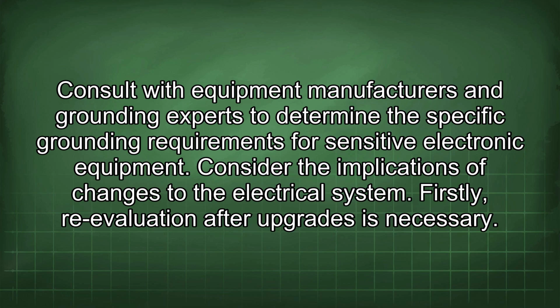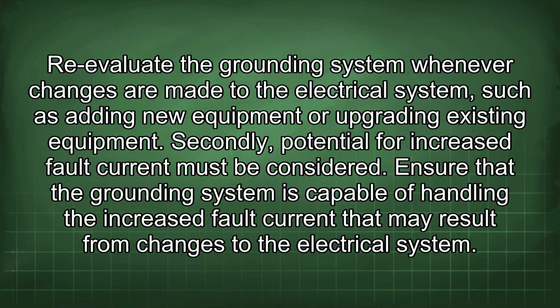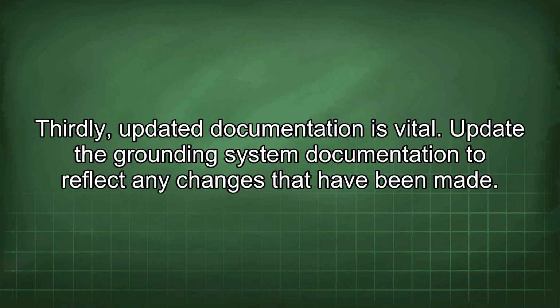Consider the implications of changes to the electrical system. Firstly, re-evaluation after upgrades is necessary. Re-evaluate the grounding system whenever changes are made to the electrical system, such as adding new equipment or upgrading existing equipment. Secondly, potential for increased fault current must be considered. Ensure that the grounding system is capable of handling the increased fault current that may result from changes to the electrical system. Thirdly, updated documentation is vital. Update the grounding system documentation to reflect any changes that have been made.